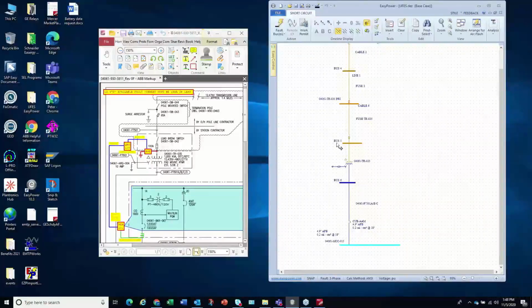And one advantage of doing this, putting your UFES on the primary side, is your transformer doesn't really get exposed to the short circuit current of the bolted fault. It only has the limited arcing fault current. So it's probably better for your transformer to do it this way, if you can do it, if you have the proper switching up above, so you're not shutting down your medium voltage system. So that's what I have. Are there any questions? Anybody like to?